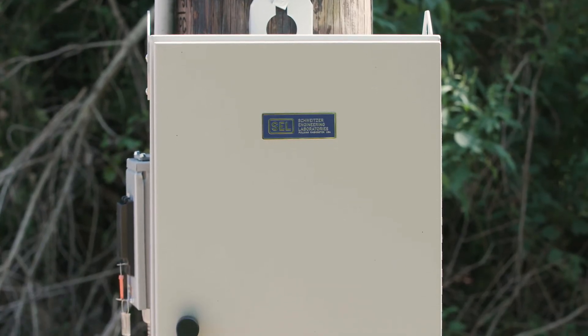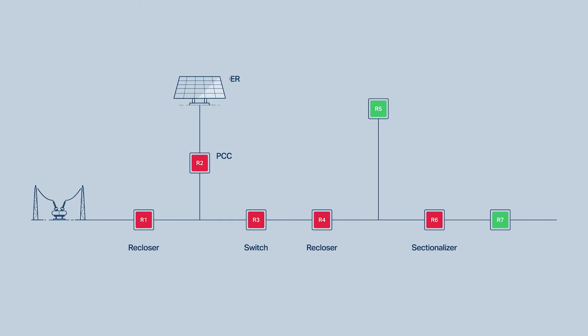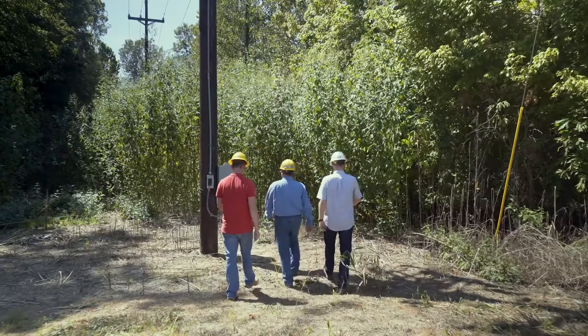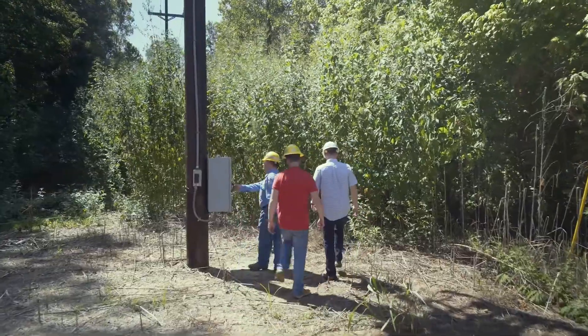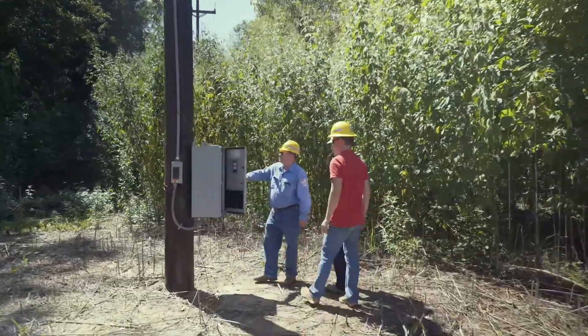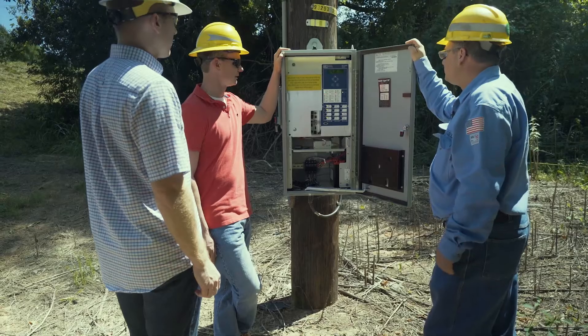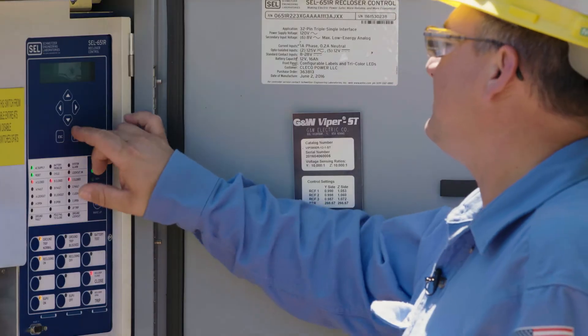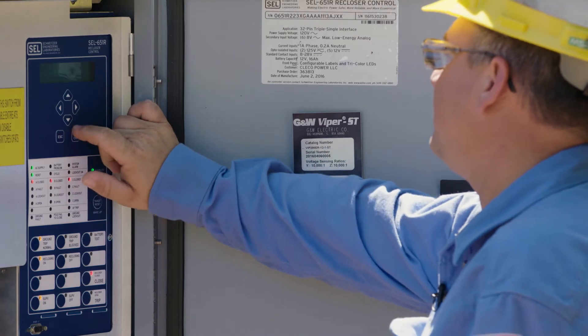We use design templates to build a pre-engineered solution for each unique application. So whether they want to use a recloser control as a recloser or as a switch, a sectionalizer, a DER microgrid controller, or at the point of common coupling, the pre-engineered design template gives them a starting off point with all the features for that application — with a consistent, familiar interface to help reduce the learning curve for them to apply the product throughout their system.